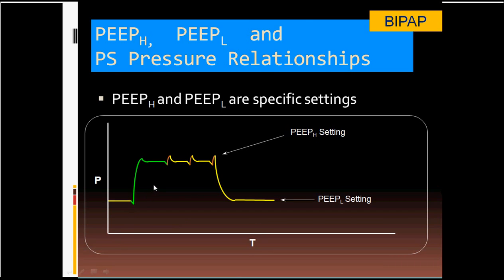The main function is that you set a lower CPAP and a higher CPAP. The higher CPAP is maintained for a set duration. The difference between these two is the driving pressure between the lower and the higher, and this will be responsible for the delivery of a certain tidal volume according to compliance and resistance. This driving pressure decides the tidal volume, and the level is preset.